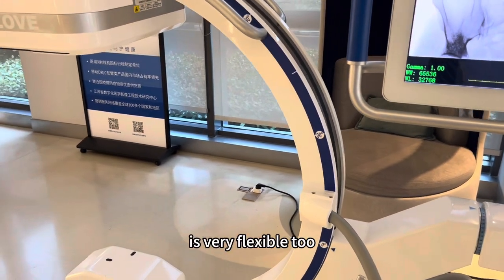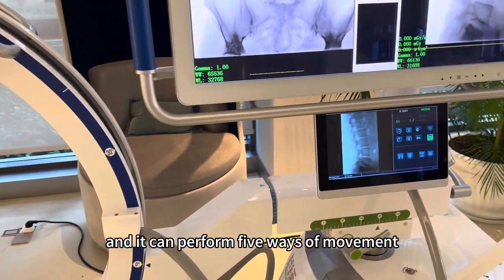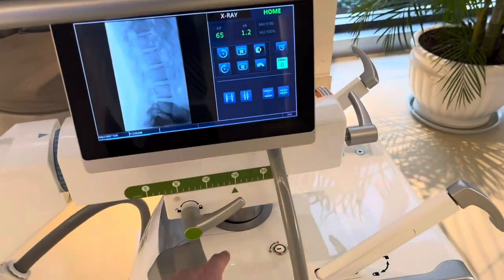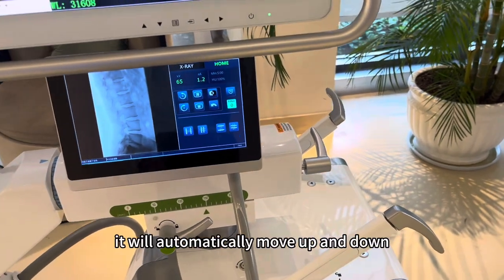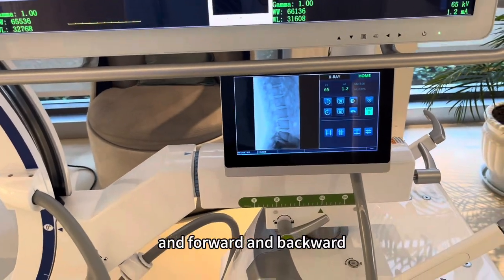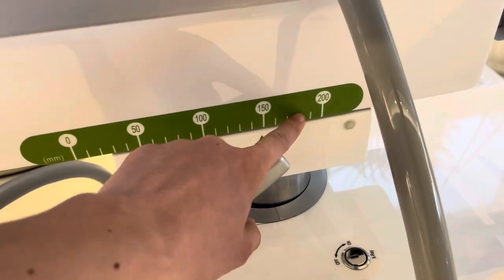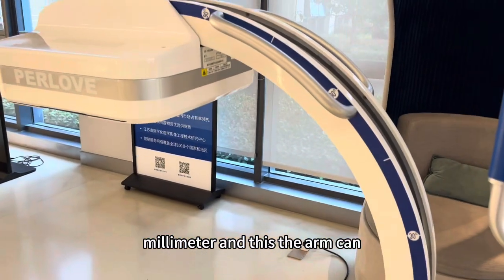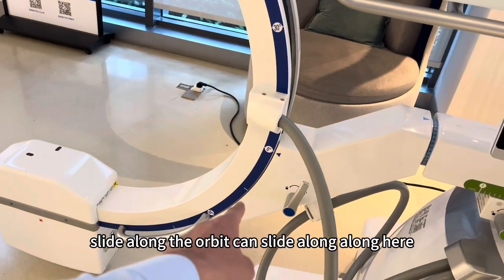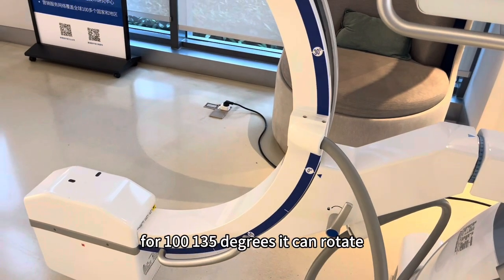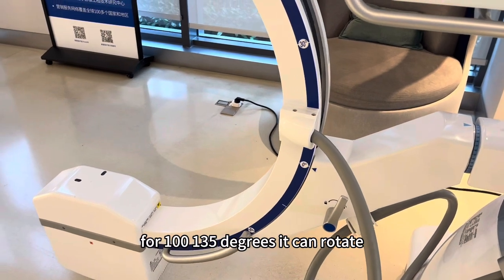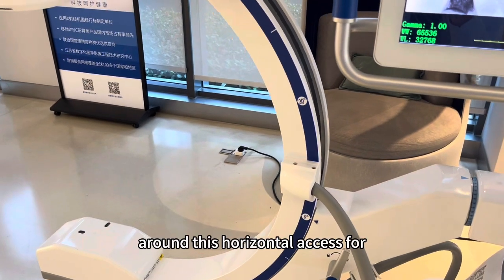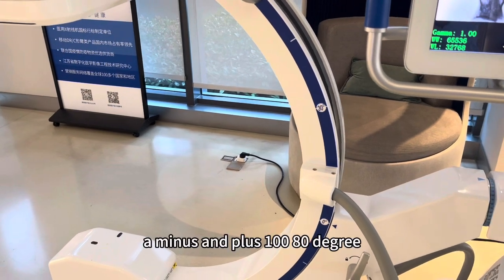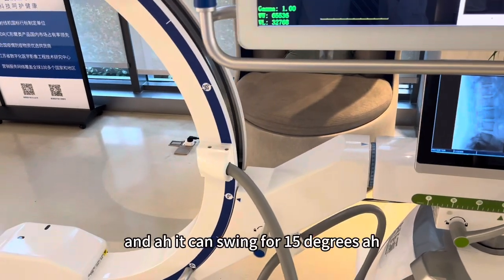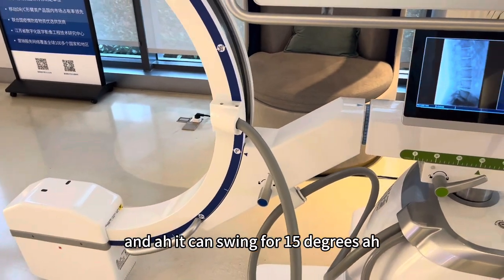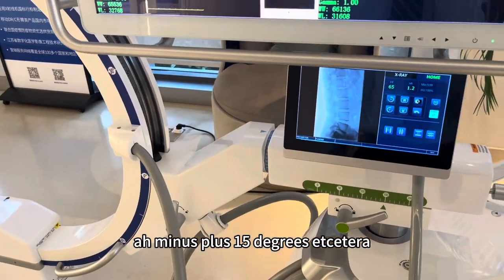It's very flexible too, and it can perform 5 ways of movement, including up and down electrical movement. Just press the button, it will automatically move up and down, and forward and backward for 200 millimeters. And this C-arm can slide along the orbit, can slide along here for 135 degrees. It can rotate around this horizontal axis for minus and plus 180 degrees, and it can swing for 15 degrees, minus plus 15 degrees, etc.